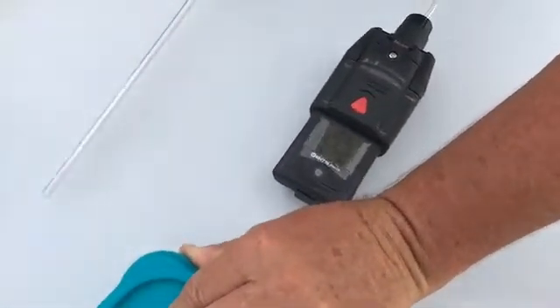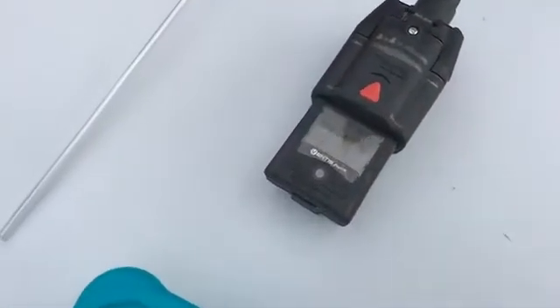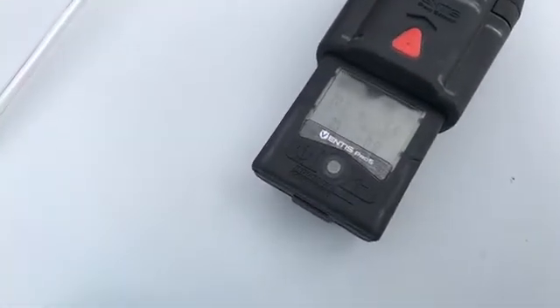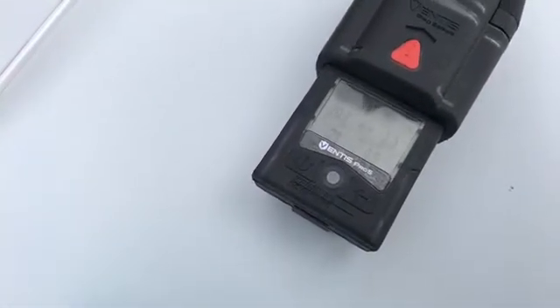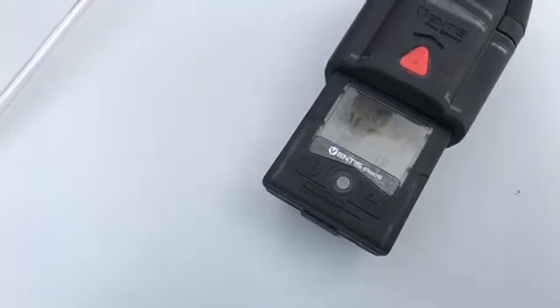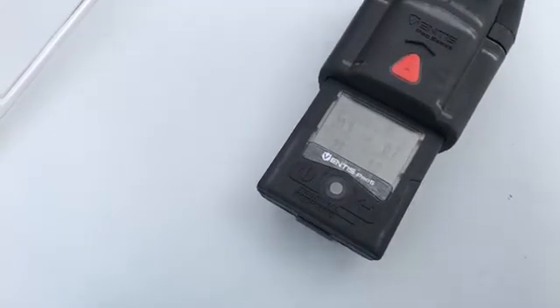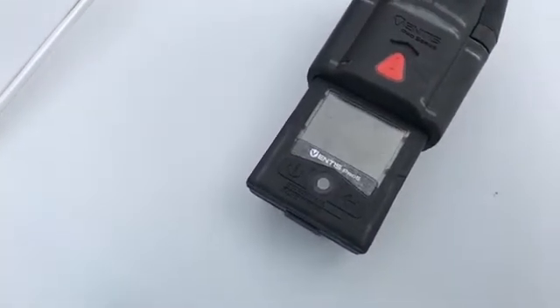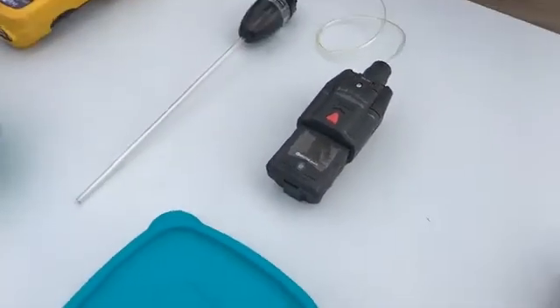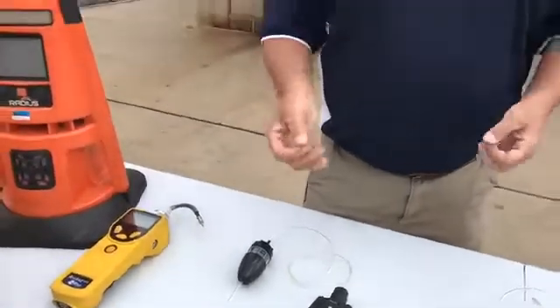So I'm going to go ahead and do the same thing here, and I'm just going to activate this monitor like we did the other ones. And you see it's going to jump up here, and you're going to get some audible and visual alarms. It's also going to flash the word evacuate up there, just telling you to take a look at your readings and back out. So it's a nice feature of the monitor, but again, we don't specifically know what that chemical is as of yet, but what we do know is we're getting a reading that we should address. We might need to back out and reevaluate what our plan's going to be. That's the Ventis Pro5.